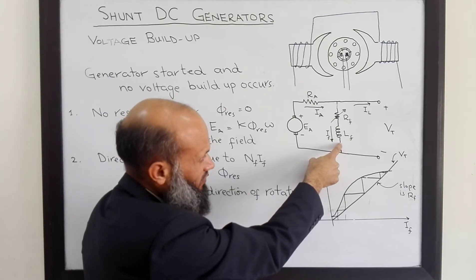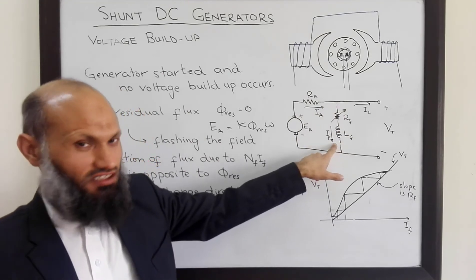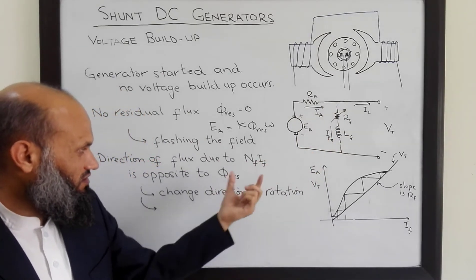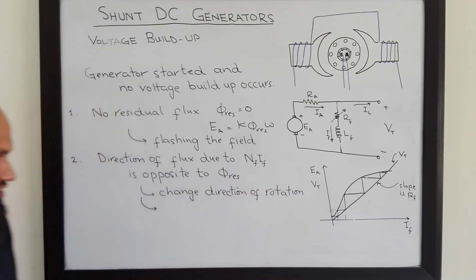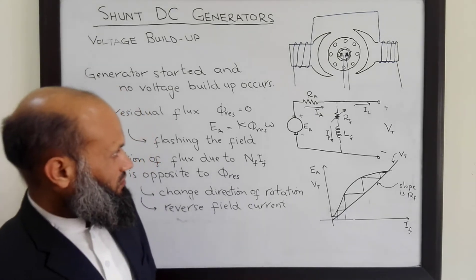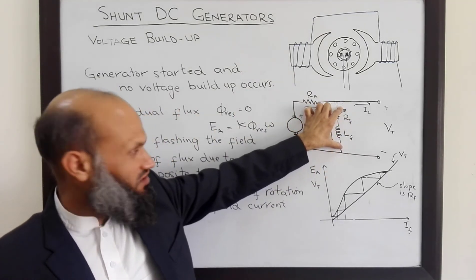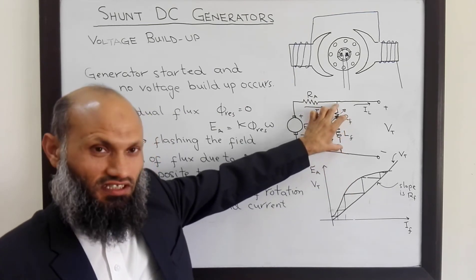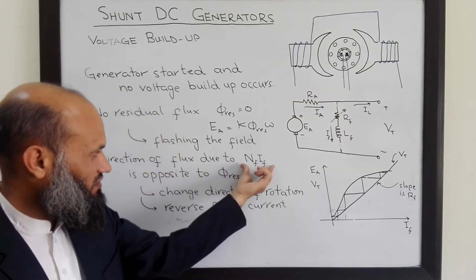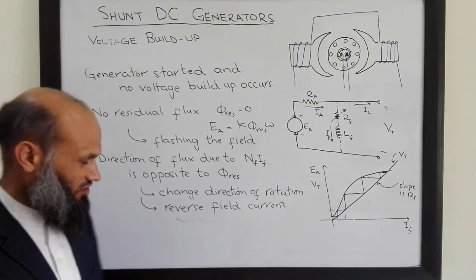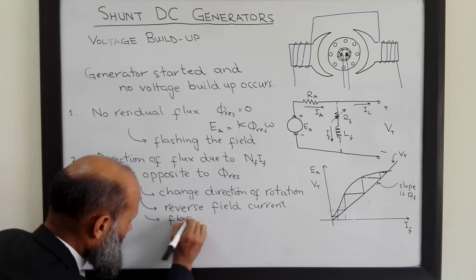The solutions to the opposing flux problem are: first, change the direction of rotation of the rotor — this reverses the direction of generated voltage and therefore the direction of current in the field winding, making both residual flux and MMF flux align in the same direction. Second, reverse the connections of the field windings, which reverses the direction of current. Third, flash the field using an external voltage source to create residual flux in the correct direction.